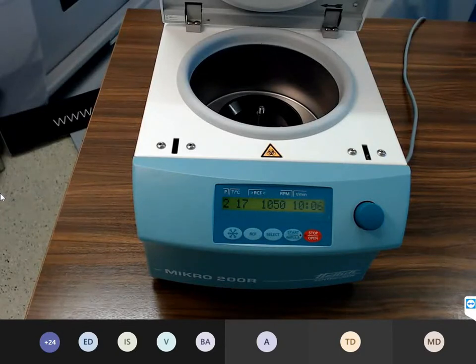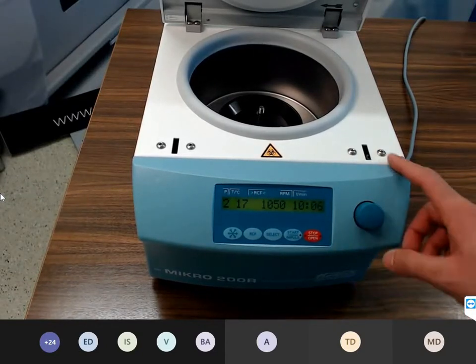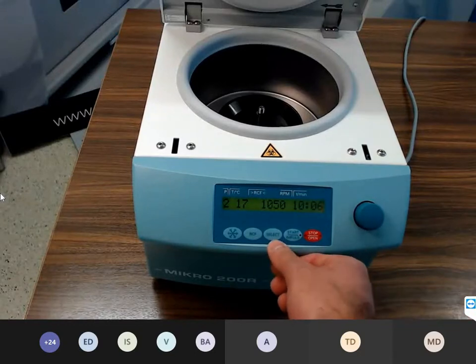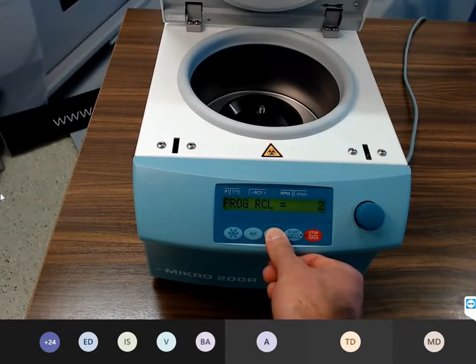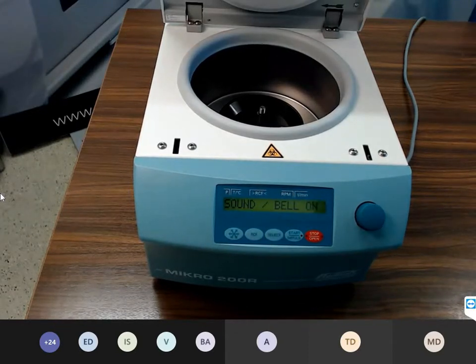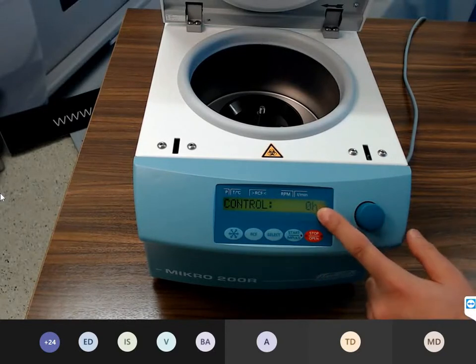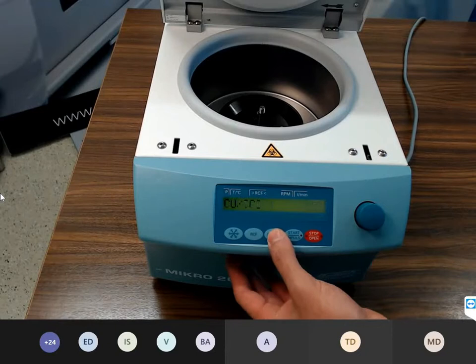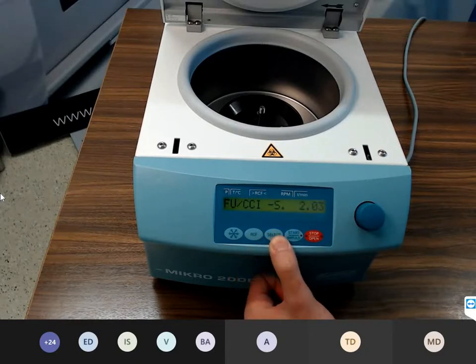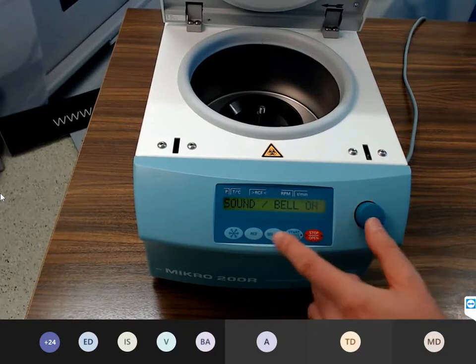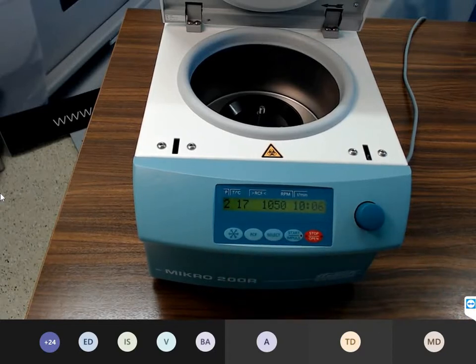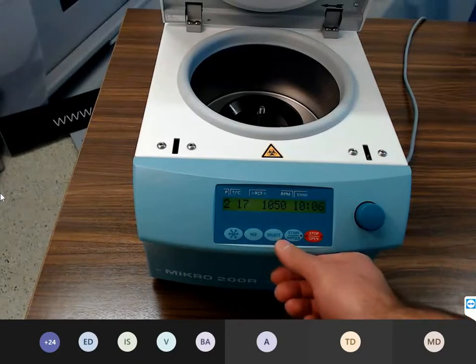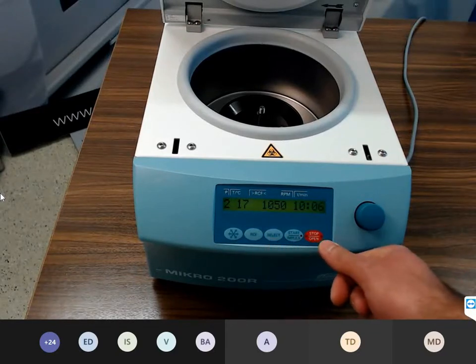Okay. So for the entry to the first menu, please hold the select key for 8 seconds. In this menu, we can adjust the sound bell, acoustic signal. We can read the control time, it's in hours. The version of the frequency converter, it's not important for you. This was the first menu. I repeat, press the select key for 8 seconds. And for the second menu, we have to press the select key for 16 seconds.